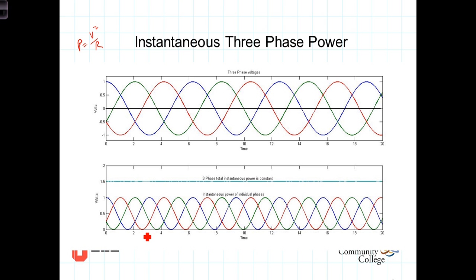Because you've got three different windings, say we're talking about a three-phase motor. Because you've got three different windings, each providing force or torque to your shaft, no one phase has to provide all of the power. So for a motor of a given power, a given horsepower, say a 15-horsepower motor, comparing a three-phase to a single-phase 15-horsepower motor, each of the phases in the three-phase motor will have less current through them and provide less torque than what the single-phase winding would need to do.